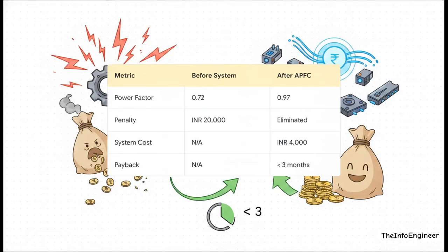The math literally speaks for itself here, and this is drawn directly from a real-world case study. By bumping up a lagging 0.72 power factor to a highly efficient 0.97, an annual 20,000 PKR penalty from the DISCO was completely wiped out. And because the hardware cost for the prototype sensors, relays, and capacitors is so incredibly low, it pays for itself in under 3 months. This is the exact definition of high ROI engineering.